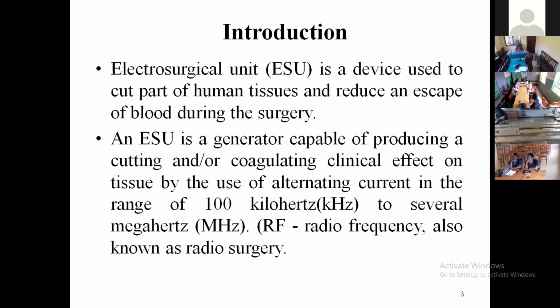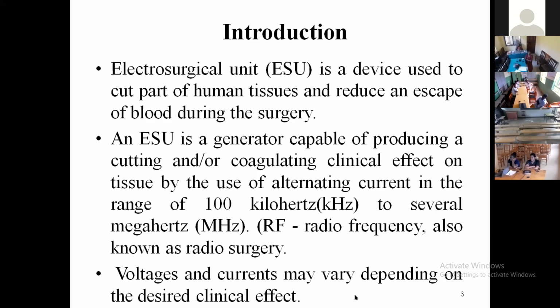Okay. So during the preventive maintenance trip for February, we did it for the three mentioned devices. But here we're going to explain just one, that is the ESU, electrosurgical unit. As we have said, an electrosurgical unit is a device used to cut a part of human tissue and reduce an escape of blood during surgery. An ESU is a generator capable of producing a cutting and coagulating clinical effect on tissue by the use of alternating current in the range of 100 kilohertz to several megahertz, that is RF, radio frequency, also known as radio surgery. Voltages and currents may vary depending on the desired clinical effect.